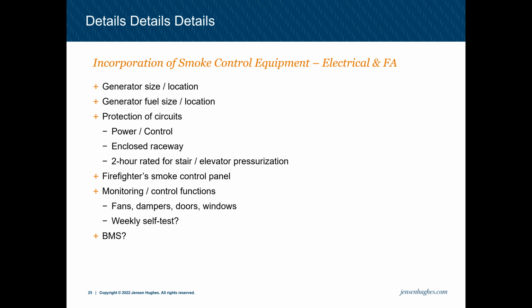smoke or stair press and elevator pressurization systems, the circuits, including power and control, must be in 2-hour protection, which if it's a new building, that's relatively straightforward to do. But if you're trying to do some retrofit of a fire alarm system to power or control a stair pressurization system, having to retrofit a 2-hour MI cable through a building with concrete floors can get very, very difficult. You're going to have to start coring the floors and figuring out the best spot that may have the least amount of impact. Then there's a firefighter smoke control panel, which we'll talk about a little bit more in more detail later on.